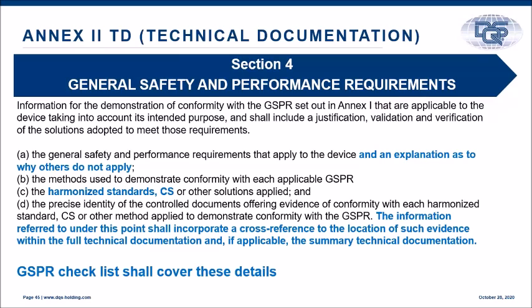The other important thing we have seen is they just give a reference like refer section so and so in the technical file, or refer risk management file. For example, if it is in the requirement, they'll say just refer risk management file, which is no longer acceptable. You need to provide a clear cross reference of the evidence within the file, or if it is outside the file, you need to provide it including the revision control. So complete information needs to be there about the reference document, which will demonstrate compliance to each of the GSPR requirements.